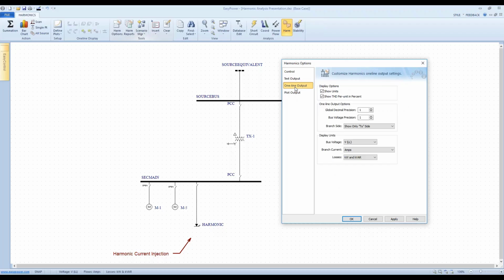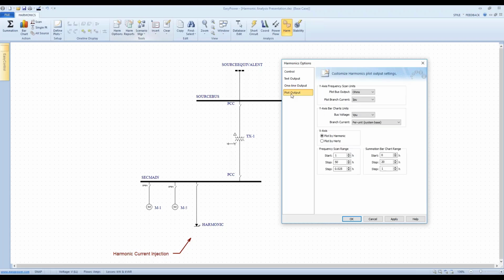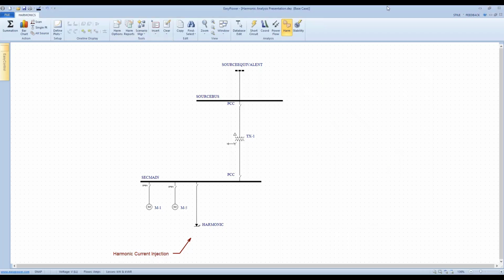From a power flow standpoint, 1 per unit makes a lot of sense, because 1 per unit power flow means you're at the rating of the equipment. If it's based on the equipment rating, or 1 per unit based on the base rating of the system. If it's 10 MVA and your devices are already 10 MVA, then it has some kind of measurable feel to what it means. And then plot output, here you can plot the branch current either in amps or in per unit. So it's key to understand what that per unit means. I think I answered that question.